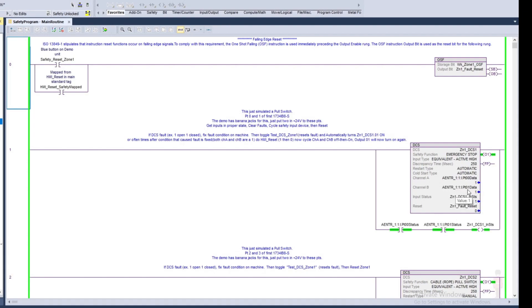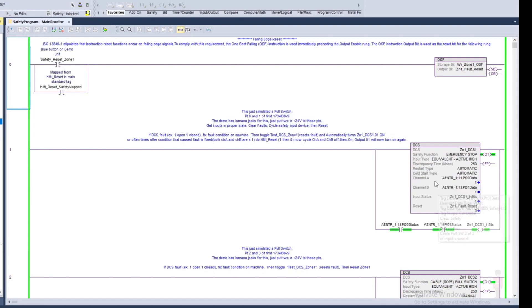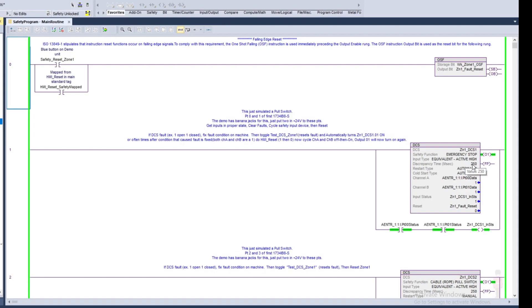I have it set up in this instance with the discrepancy time of 250 milliseconds. I could set that any different ranges. What the discrepancy time does is tells you I'm going to expect to see both contacts opening or closing within that amount of time.